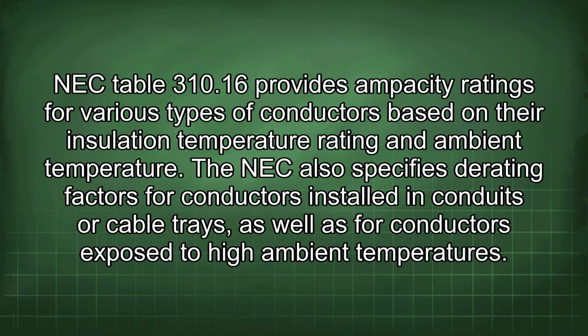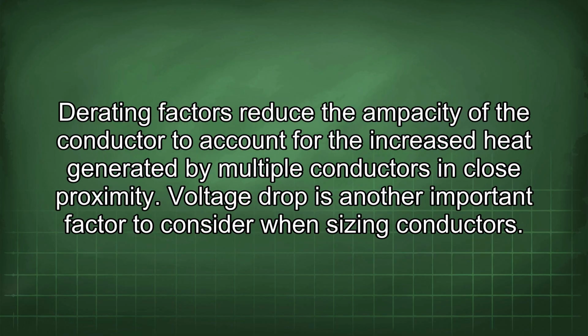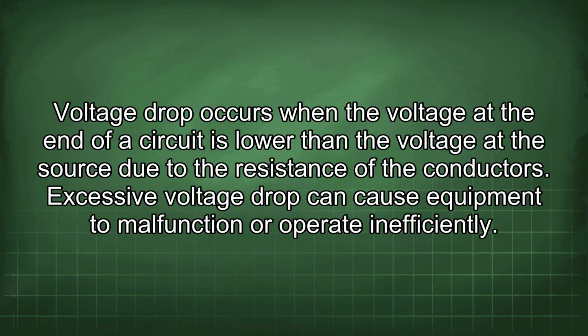The NEC also specifies derating factors for conductors installed in conduits or cable trays, as well as for conductors exposed to high ambient temperatures. Derating factors reduce the ampacity of the conductor to account for the increased heat generated by multiple conductors in close proximity. Voltage drop is another important factor to consider when sizing conductors. Voltage drop occurs when the voltage at the end of a circuit is lower than the voltage at the source due to the resistance of the conductors.